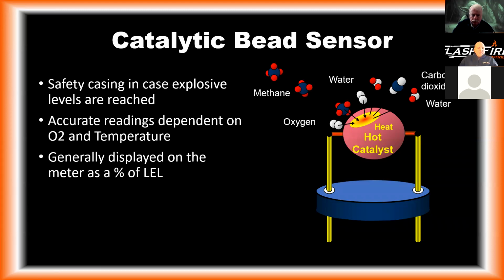The one thing to remember about our LEL sensor is that it is dependent on temperature and O2. As our temperature changes, as our oxygen levels change, we know that gas flammability can change as well. Again, this isn't something that we're going to be calculating or figuring out on scene, but just realize that if your O2 levels are changing, then potentially the readings you're getting on your LEL sensor may not be 100% correct.